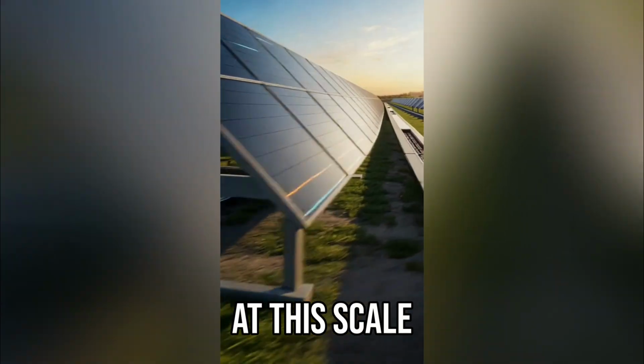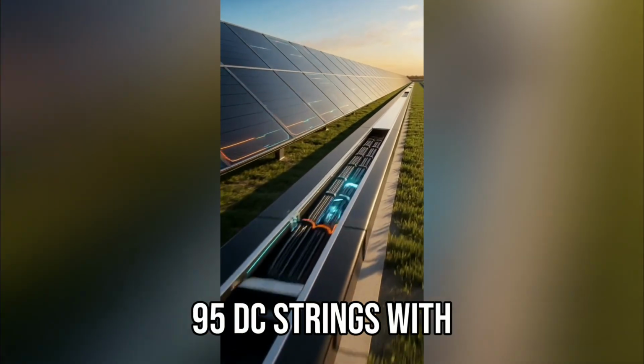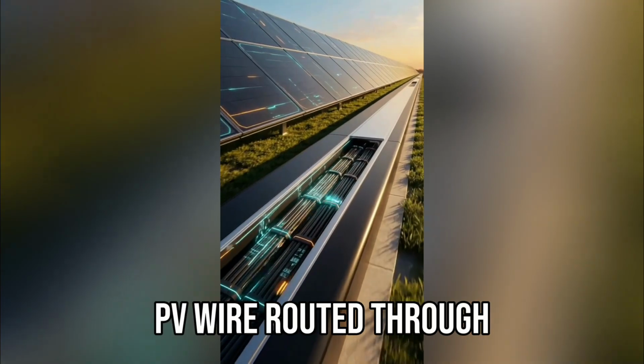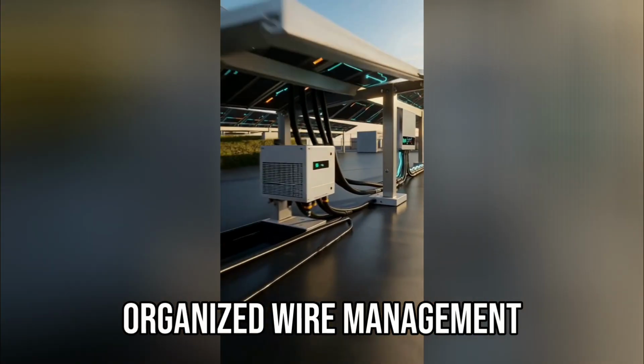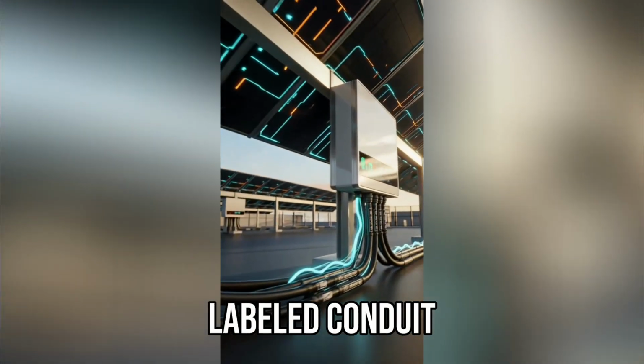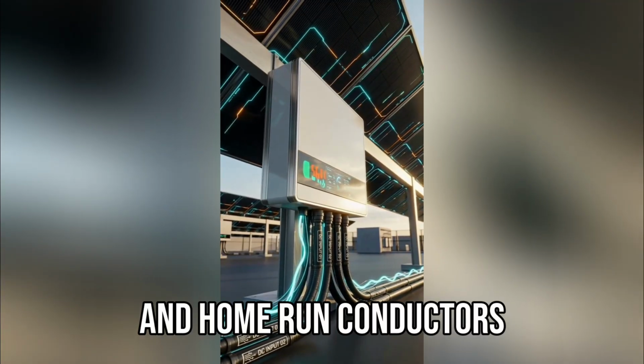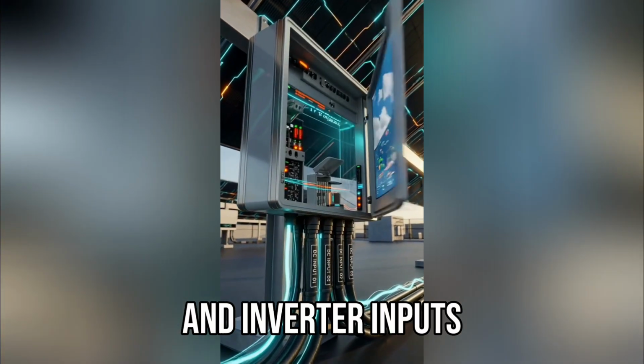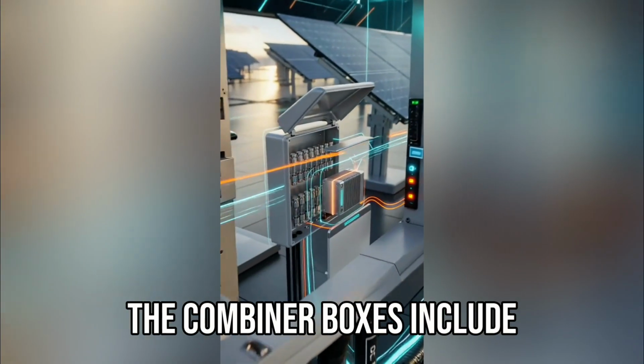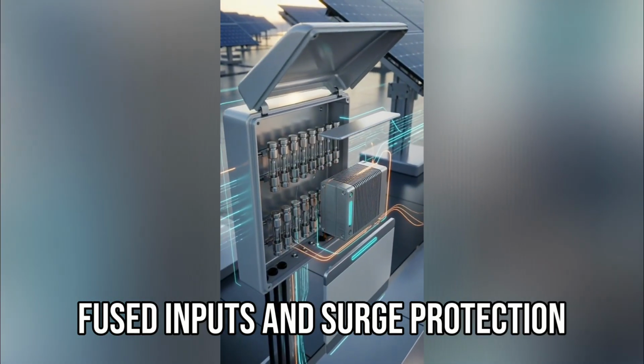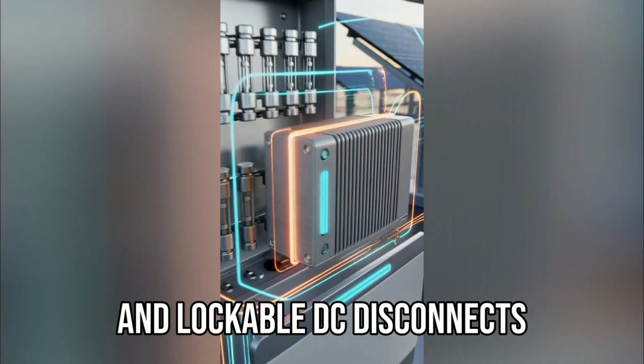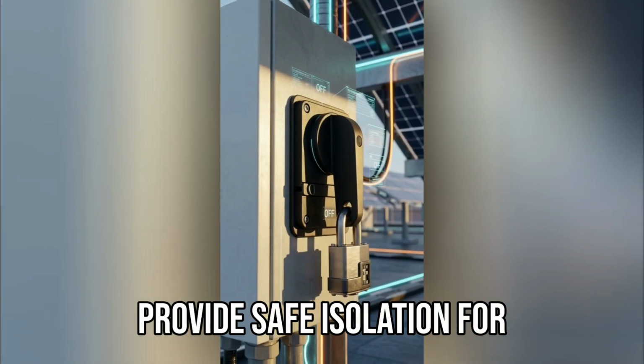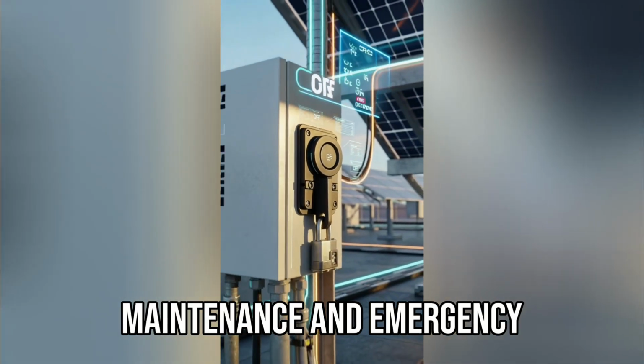At this scale, the system has about 95 DC strings, with PV wire routed through organized wire management, labeled conduit, and home-run conductors to string combiner boxes and inverter inputs.